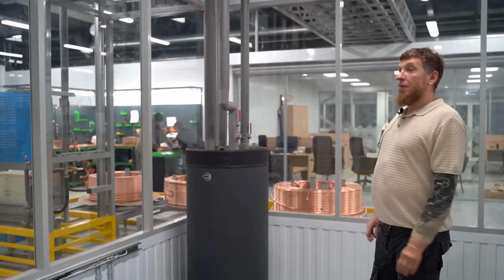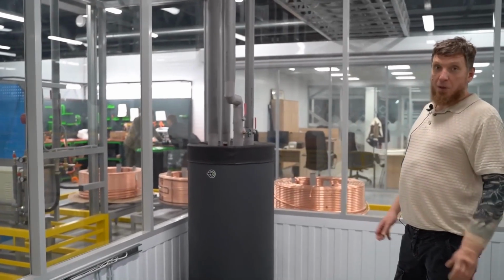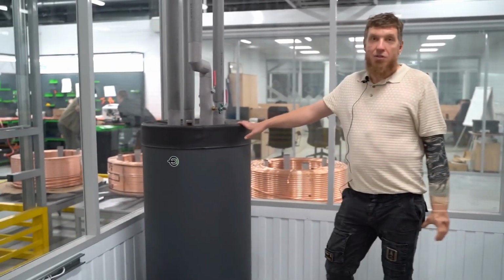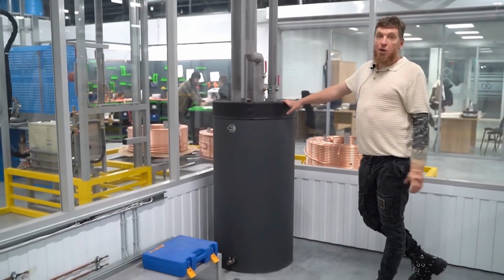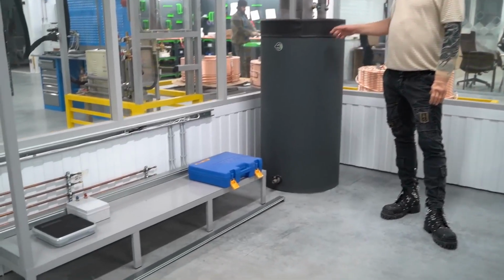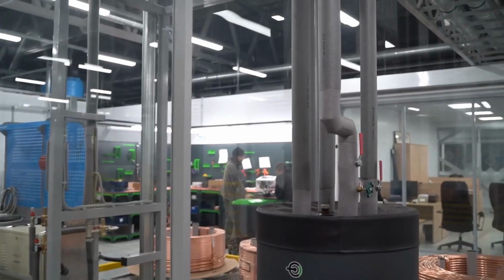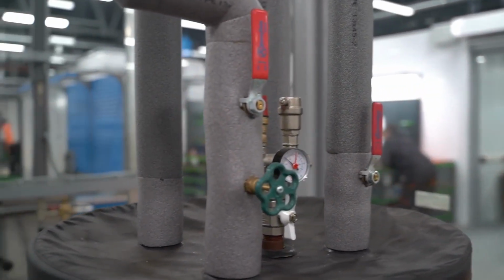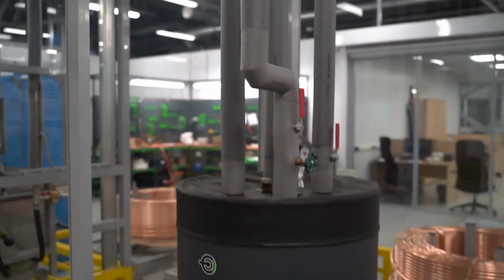Besides, it's not particularly difficult or complicated to set up this system, since we manufacture heat pumps, which are energy-saving heating devices, and within our own factory, we are very attentive to energy conservation. For example, you see this 500-liter tank here. What is it for? When the inductor is operating, it is cooled by water. Water cooling is absolutely necessary. And through this buffer, the excess heat, depending on the season and so on, is either diverted to heating or for preheating the domestic hot water, but if there's nowhere else to divert it, then through a heat exchanger it goes into our fire pond. In other words, we never just dump water anywhere. We apply this approach to all our systems. So when the factory is running at full capacity, all the heat from the inductors, which generate quite a lot, will be used to heat the building.